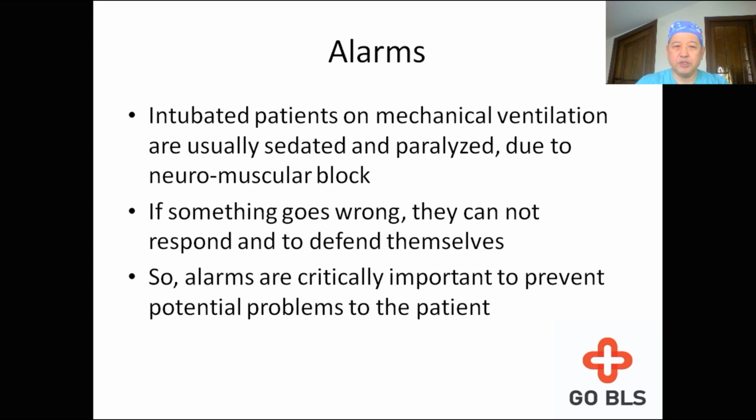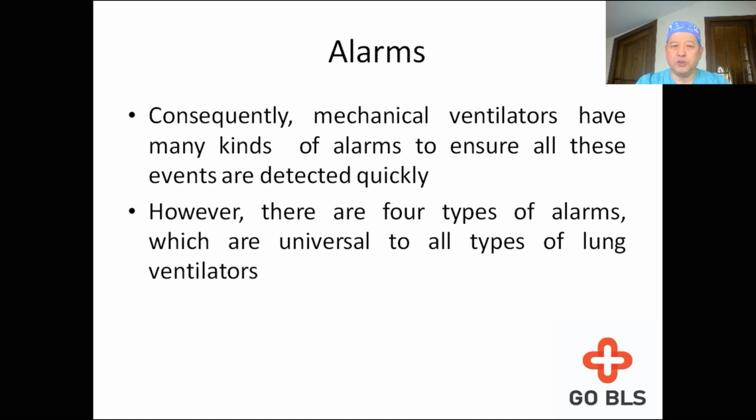Now let's talk about alarms. As I said to you before, intubated patients on mechanical ventilation are usually deeply sedated and paralyzed due to neuromuscular block and due to sedative drugs. So if something goes wrong, they cannot respond and they cannot defend themselves. So alarms are critically important to prevent potential problems to the patient. Consequently, mechanical ventilators have many kinds of alarms to ensure all these events are detected quickly.